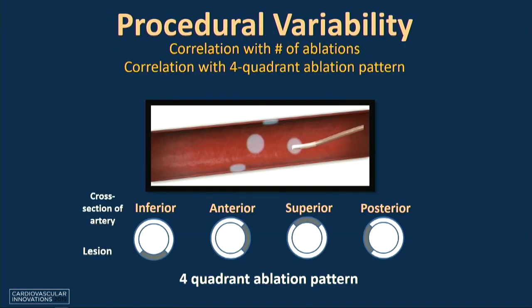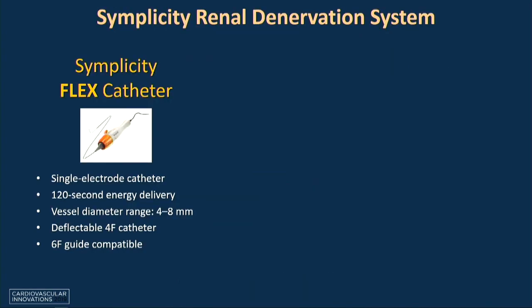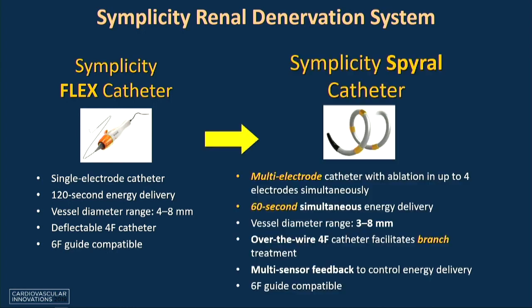With the early iteration of the catheters, the number of ablations correlated with a better treatment. So the operator has to ablate in 4 quadrants and make sure all 4 quadrants are ablated, which, you understand, can technically be sometimes undoable or hard to do. This is the Symplicity Flex catheter. It is a single-electrode catheter with 120-second energy delivery and a vessel diameter from 4 to 8 millimeters, and it goes through a 6 French compatible guide, and the deflector goes through a 4 French catheter.